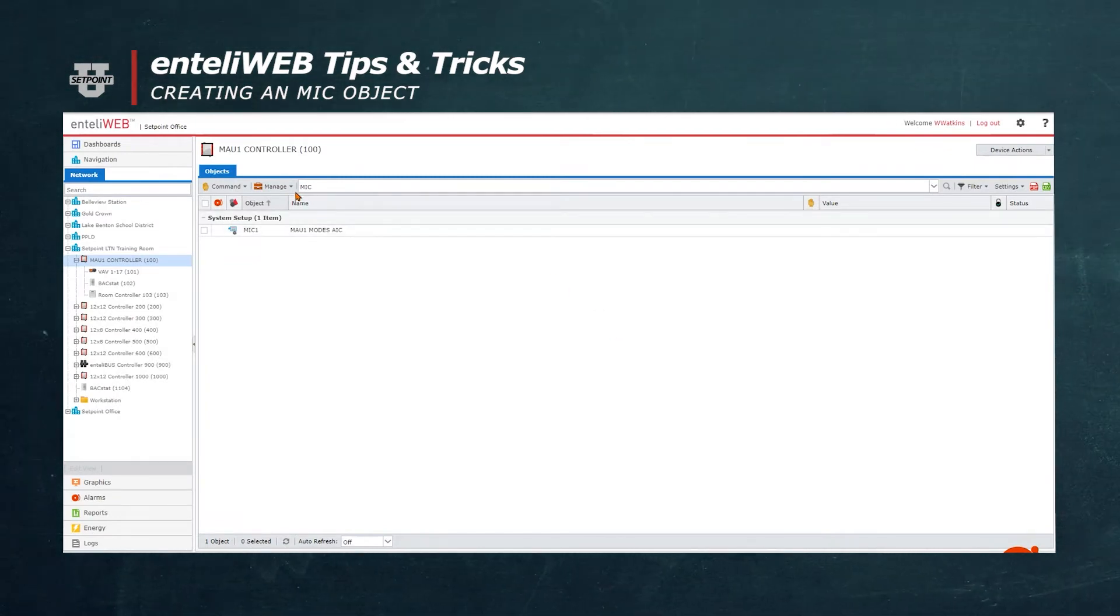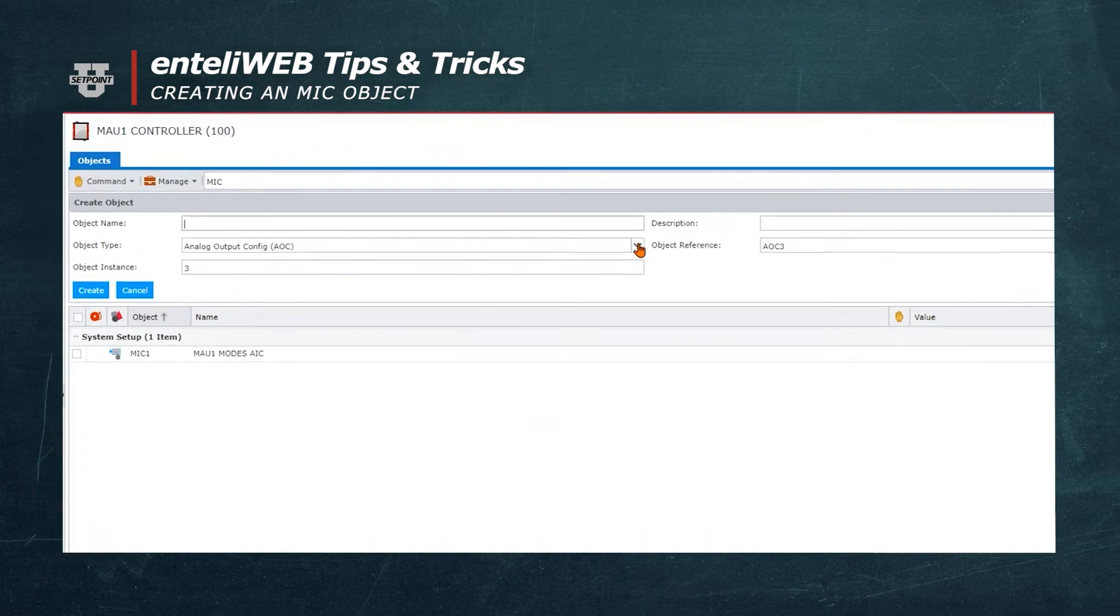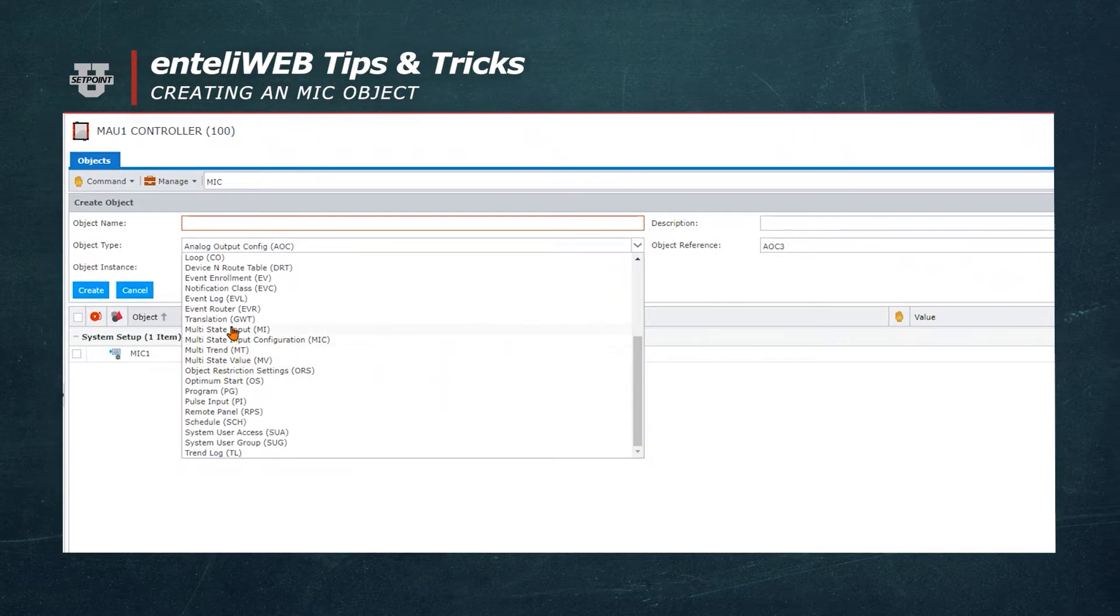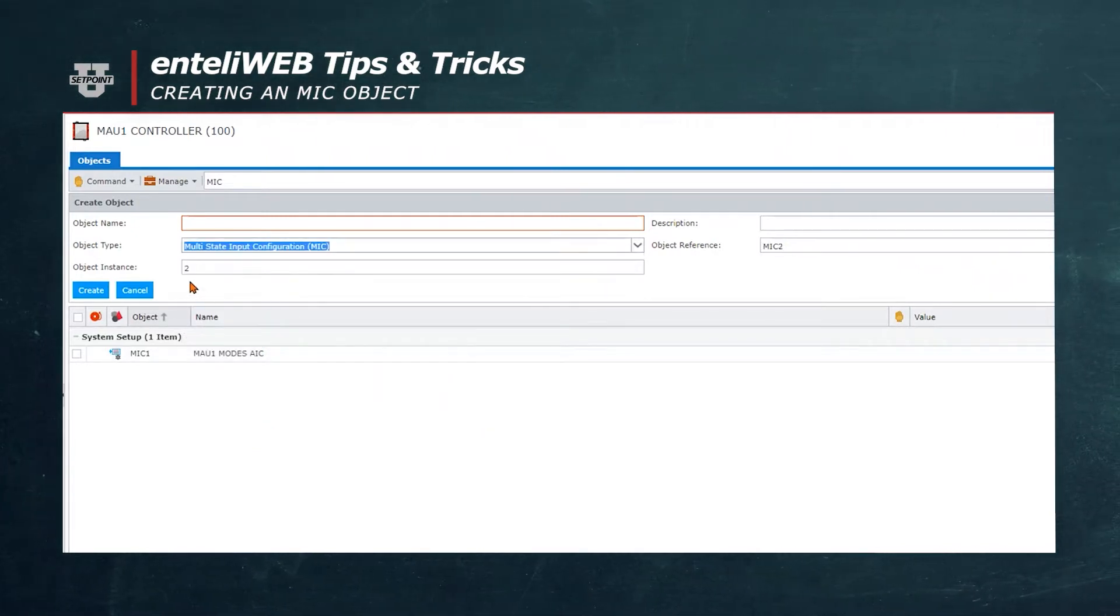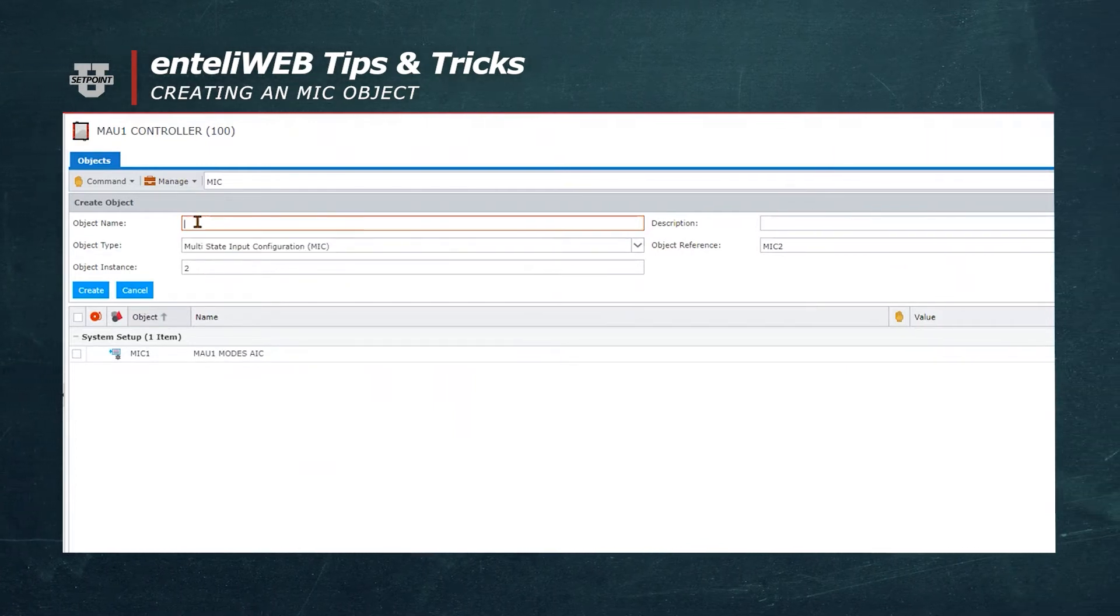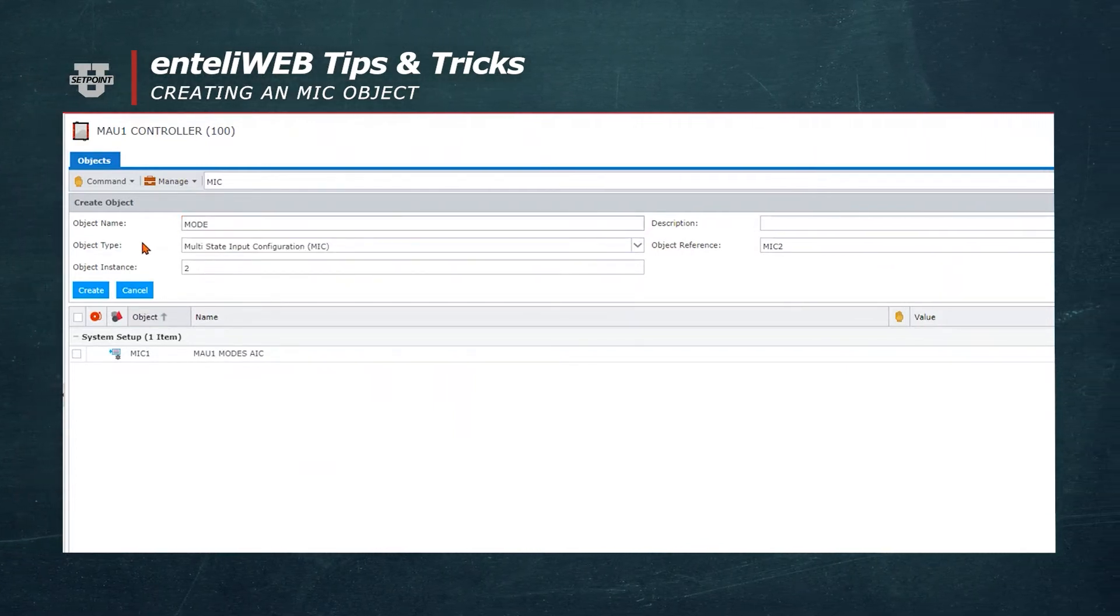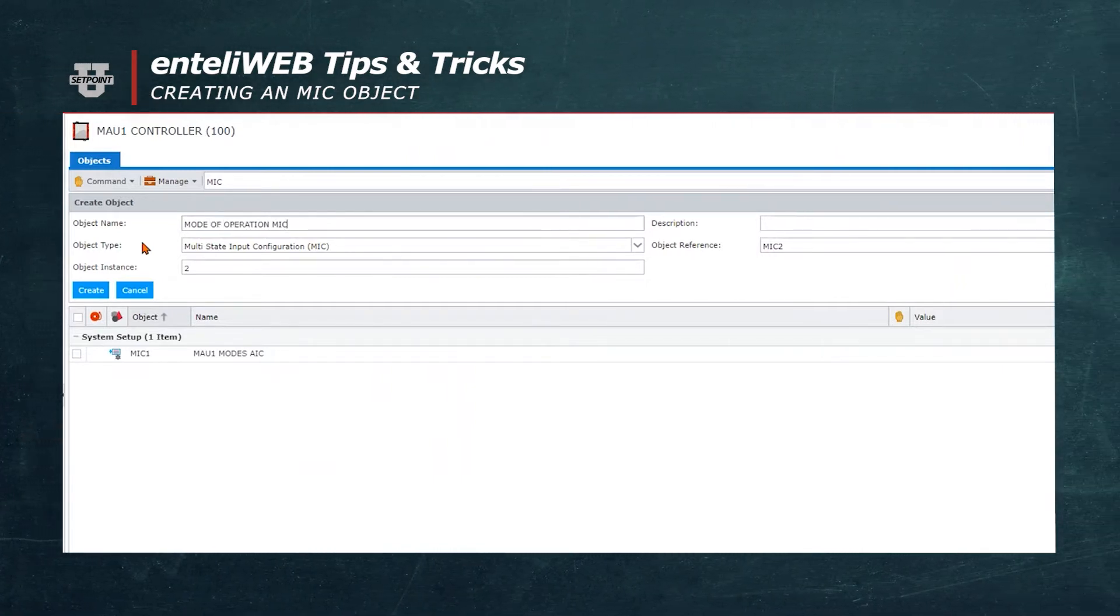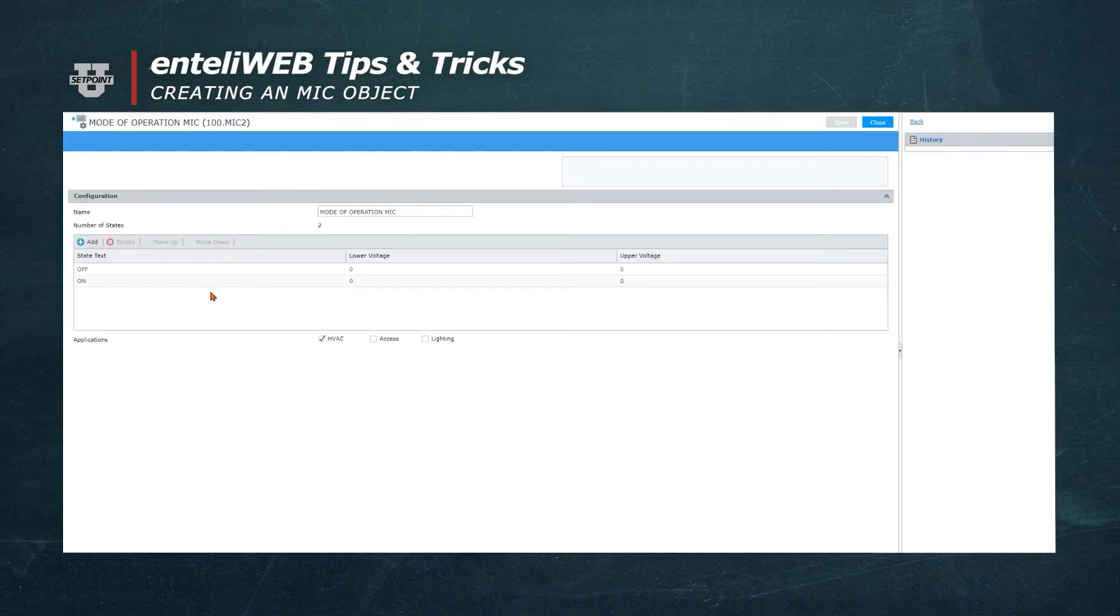Let's select the Manage button and go to Create. Then select MIC as the type of object. We'll select MIC, Multistate Input Configuration. You'll notice that it automatically went to the next available instance, which is number 2. We're going to name it Mode of Operation MIC. Now we're going to select Create, which allows us to fill in the blanks.